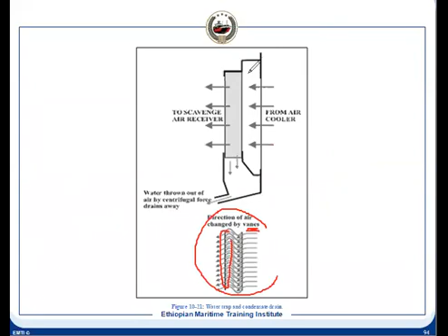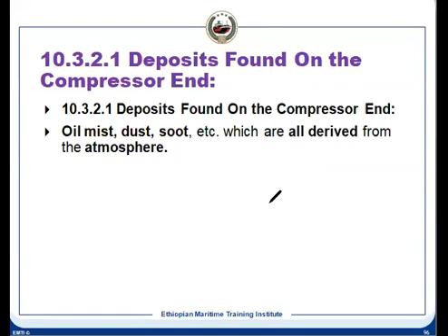Now the cleaning of turbocharger and air cooler. Now, why do you need cleaning, and where do the deposits come from? In the compressor side, what do you have? Oil mist. From where is the oil mist coming? Because in the engine room, the air contains oil mist, because it is not pure air in the engine room. There are fumes and all that mixed with the air, and there will be dust, there will be soot. All these things can make a deposit on the compressor side. So this is all derived from the atmosphere.